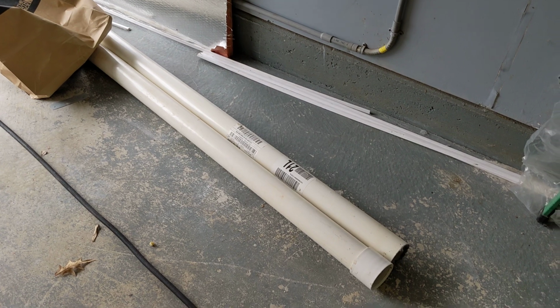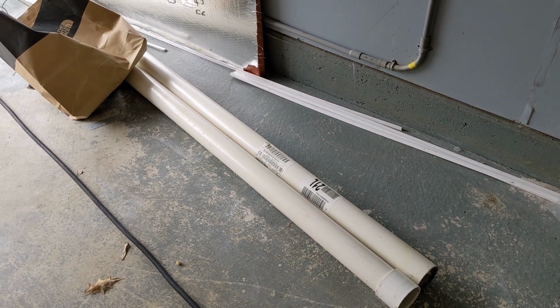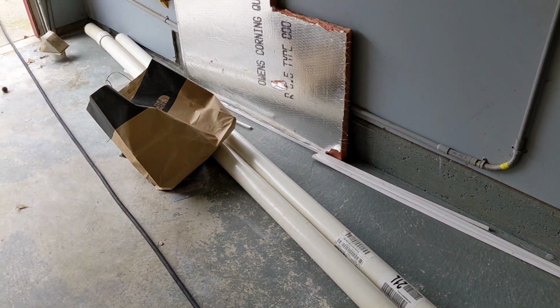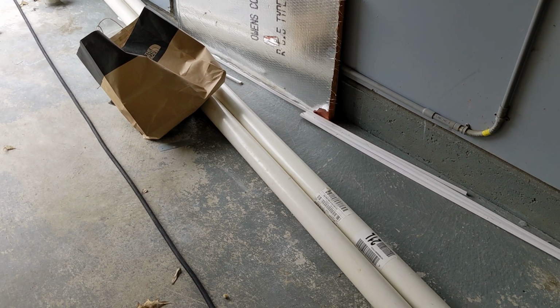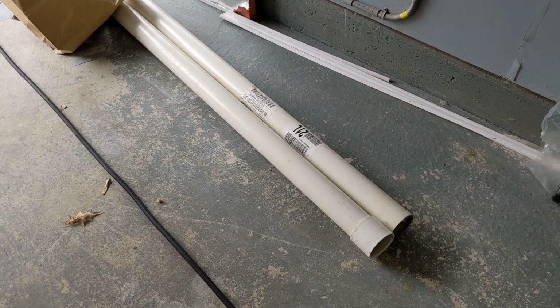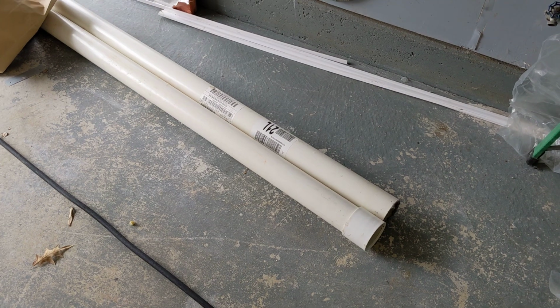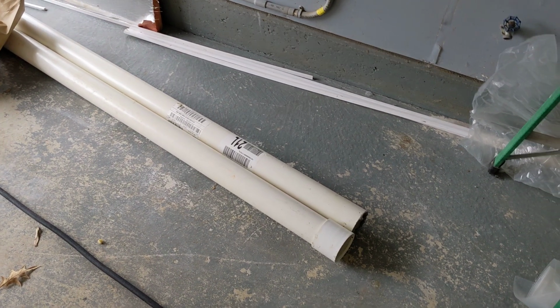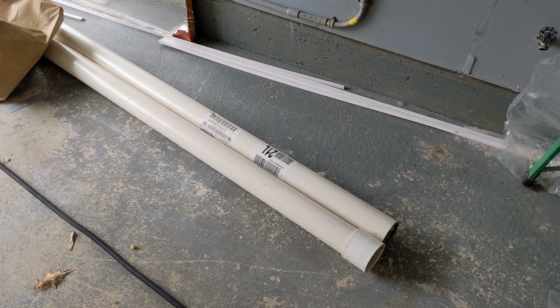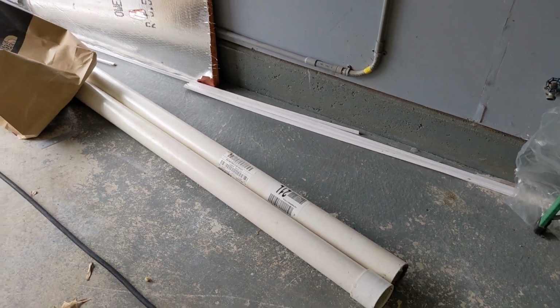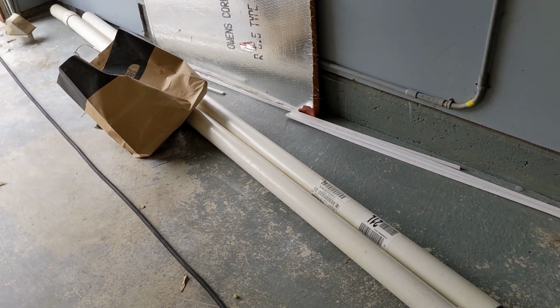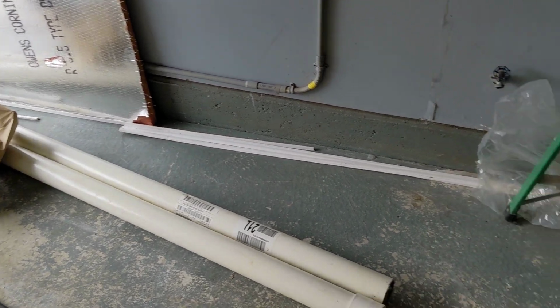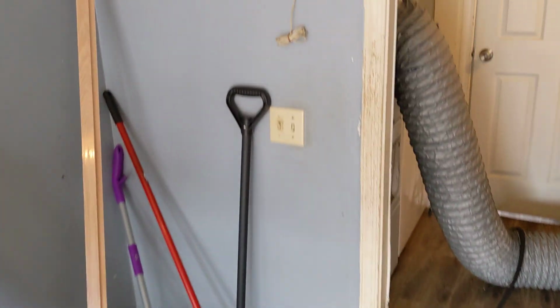Obviously the dryer gets extremely hot. It needs to discharge this hot air. If this ductwork, or this PVC piping in this case, is all clogged up with that dust and dirt and debris and lint and everything else, that hot air can't be discharged, and it just builds up heat inside the system and then ends up causing a fire. So it definitely is a fire hazard and should be cleaned. Good thing we're taking care of that as well.